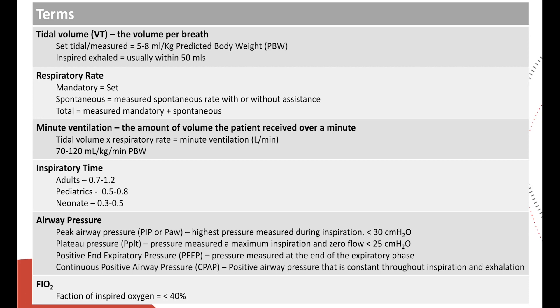When it comes to respiratory rate, there are several different types. There's the mandatory rate, which is a set rate — let's say 10. There's the spontaneous rate, which measures how many times the patient actually took a spontaneous breath with or without a assist from the ventilator. And then the total respiratory rate, often the biggest number on most ventilator screens, is mandatory plus spontaneous. So if you see a total rate of 20 and the mandatory is set at 10, the patient is breathing spontaneously 10 additional times.